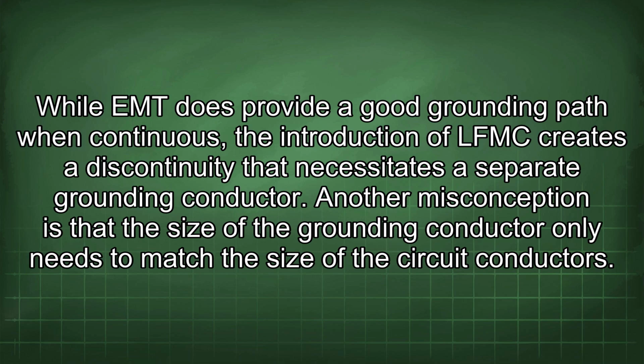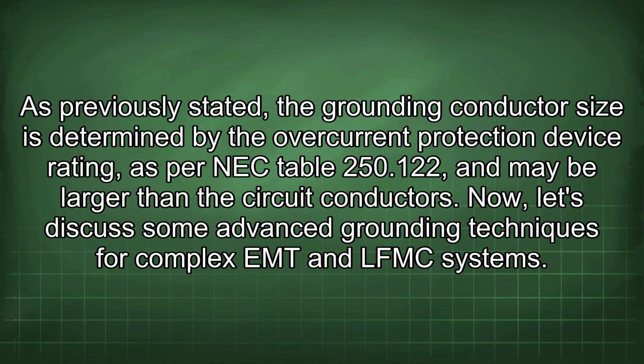separate grounding conductor. Another misconception is that the size of the grounding conductor only needs to match the size of the circuit conductors. As previously stated, the grounding conductor size is determined by the overcurrent protection device rating as per NEC Table 250.122 and may be larger than the circuit conductors. Now, let's discuss some advanced grounding techniques for complex EMT and LFMC systems.